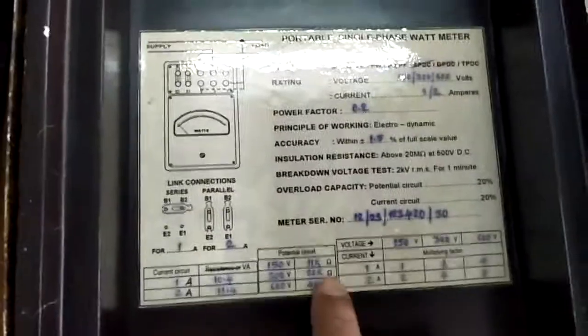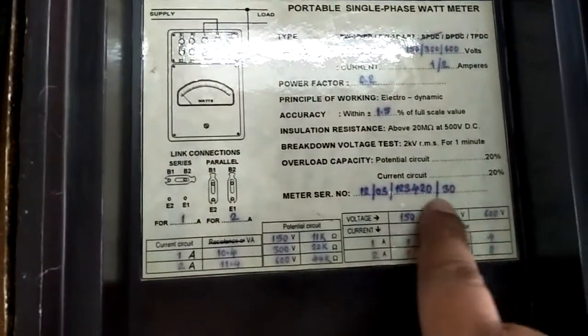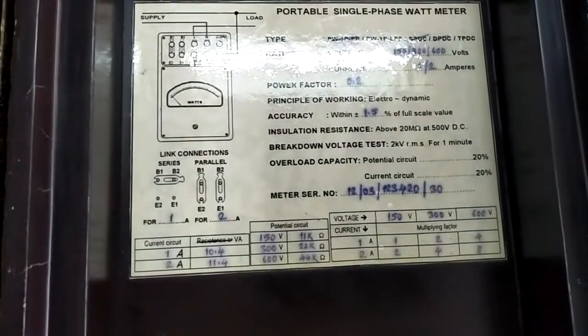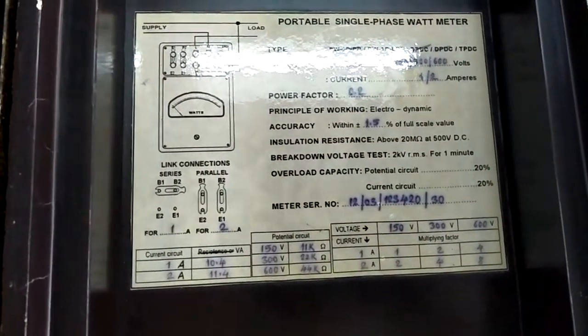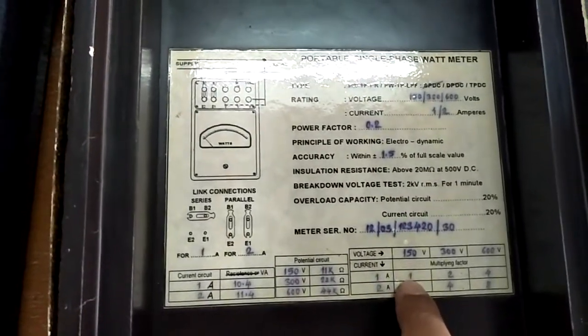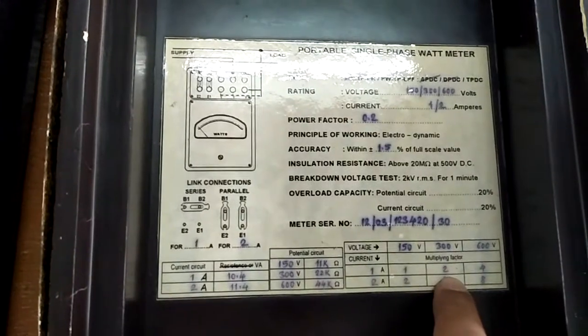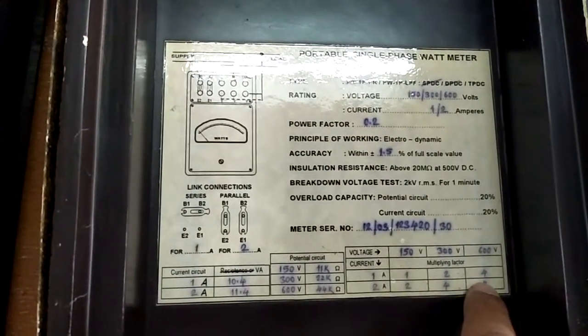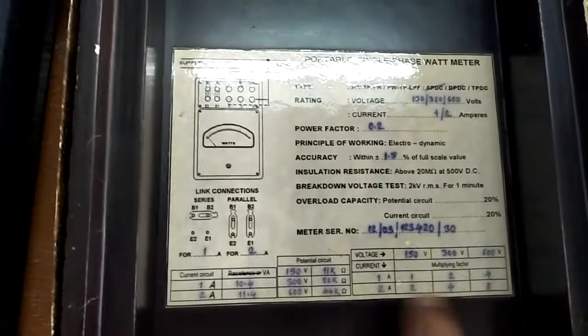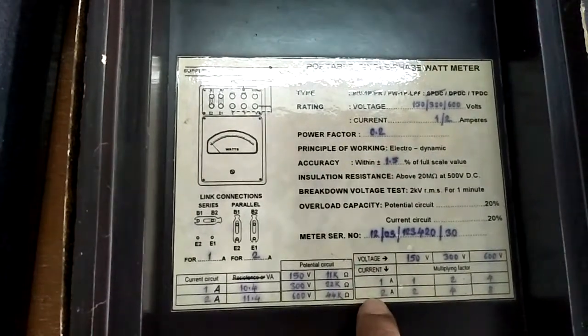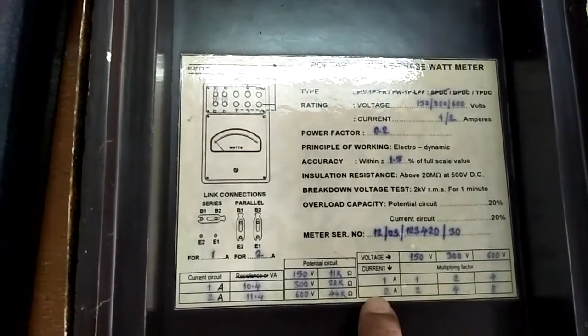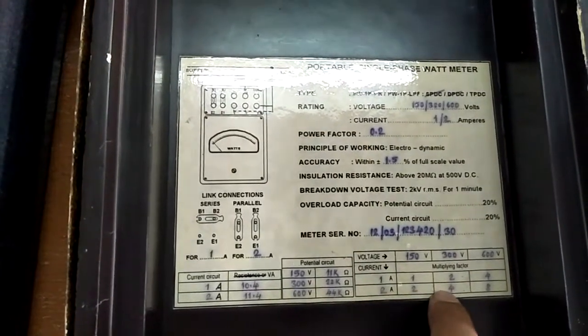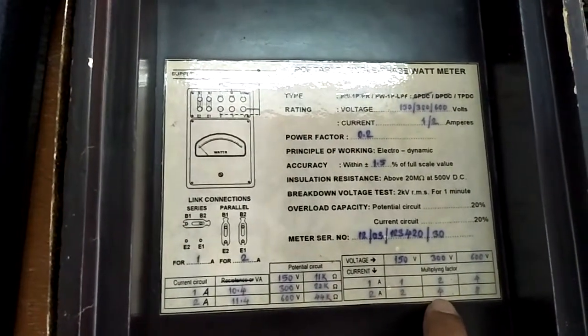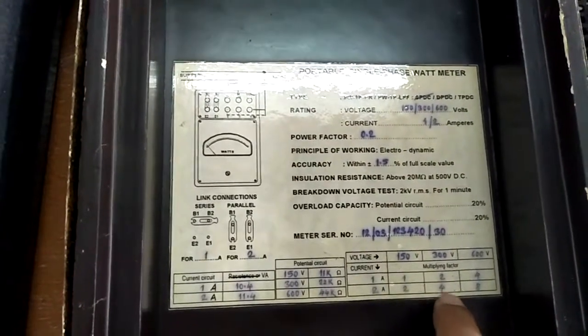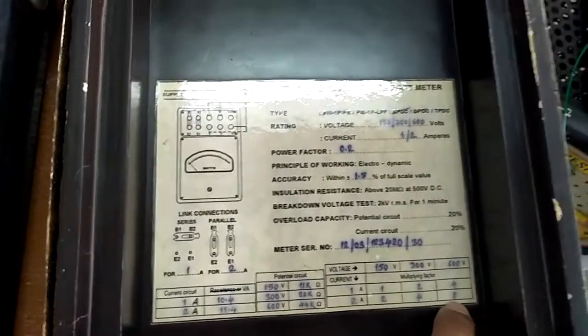So see here, this is the current range and this is the voltage range. If you select current range 1 ampere and voltage range 150 volt, then the multiplying factor is 1. If the voltage range is 300, the multiplying factor is 2. If the voltage range is 600, the multiplying factor is 4. Now if the current range is 2 ampere, which in our case we have selected, and the voltage range is 300, the multiplying factor is 4. If our voltage range is 600, then the multiplying factor is 8.